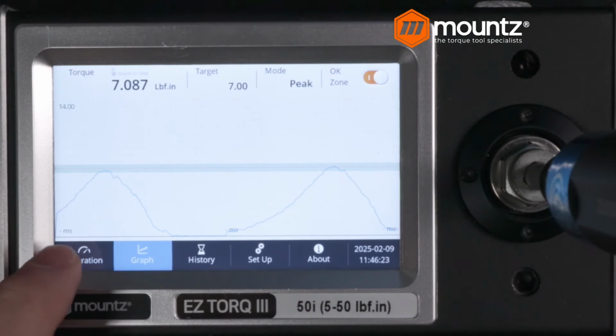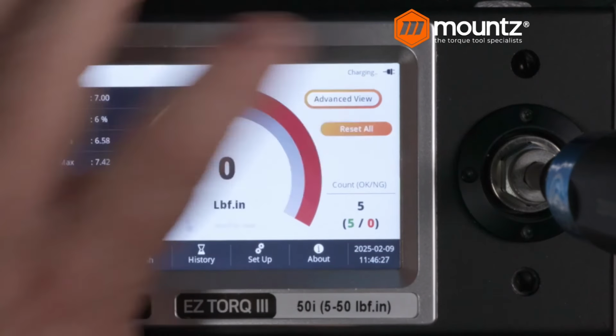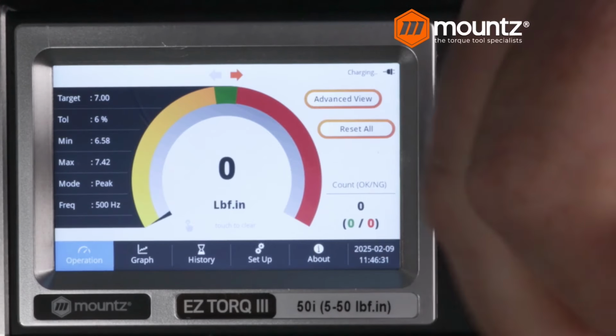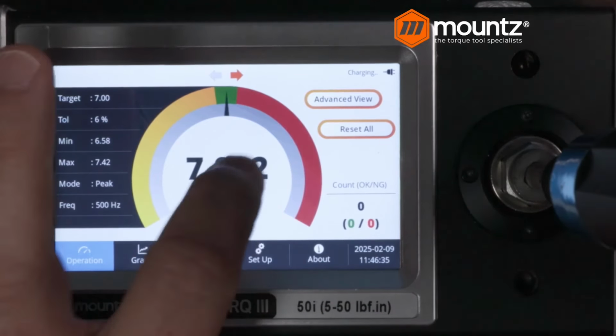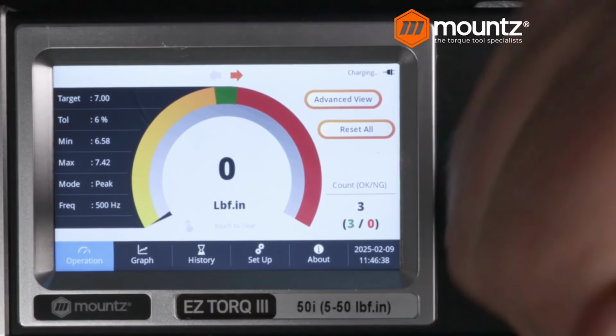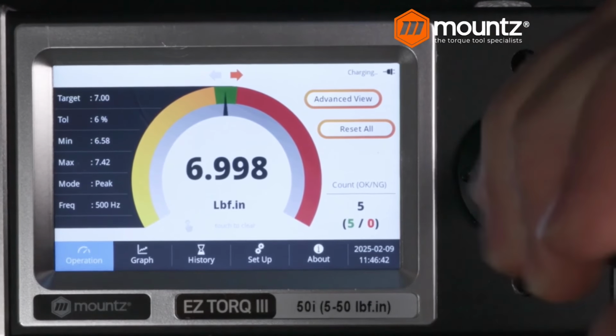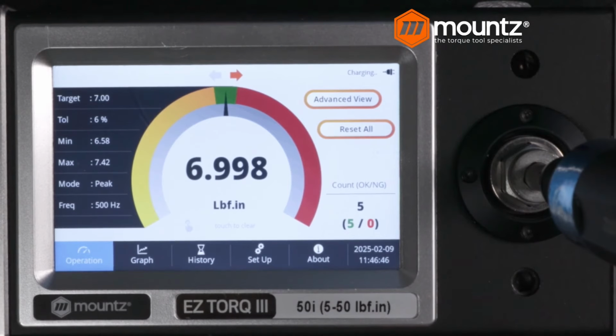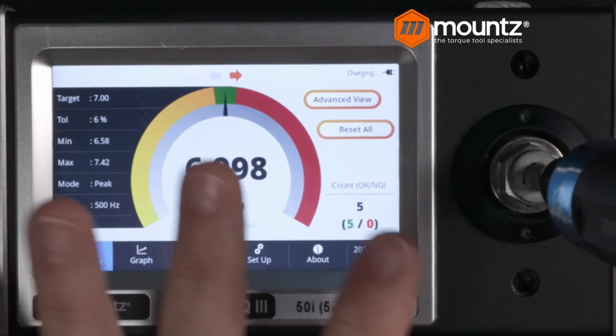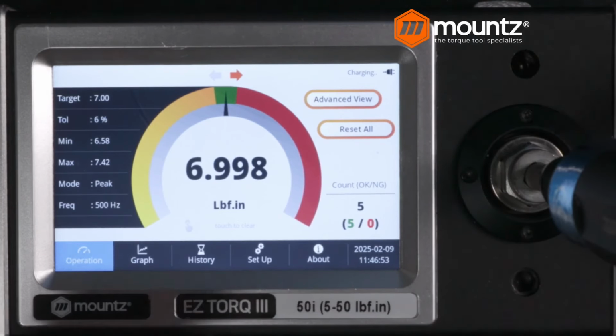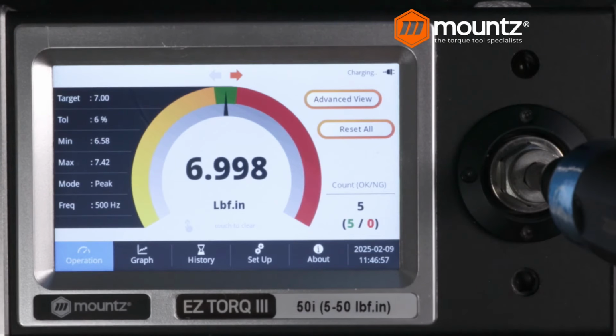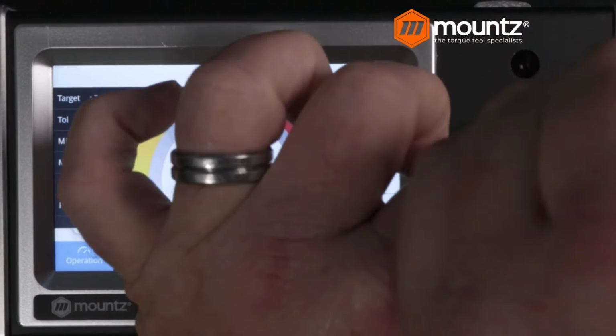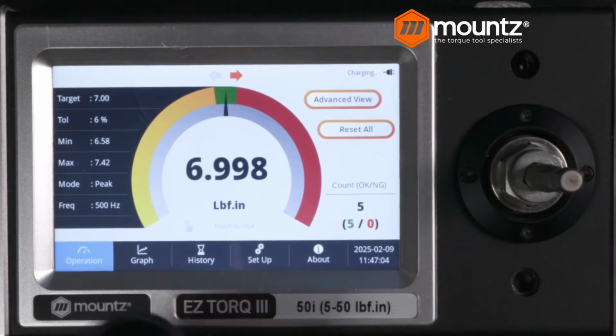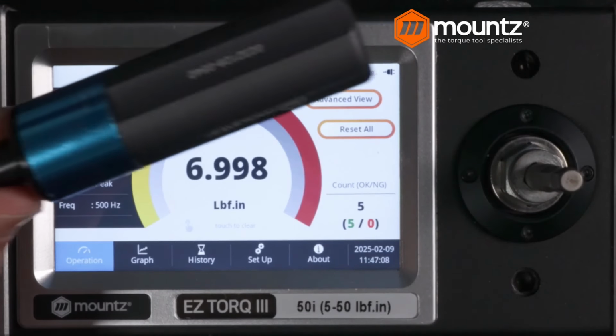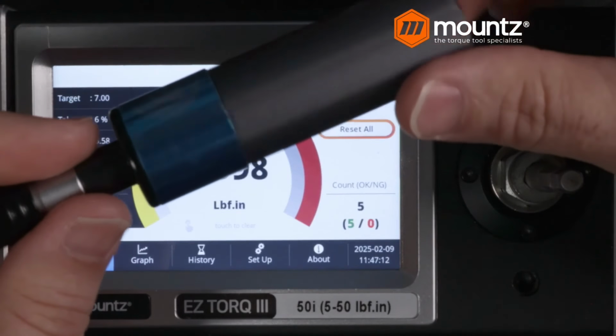Now if we come back to our operation screen, we can take our readings to see if this tool is still performing correctly. So 7 there. All right, perfect. Now we've taken our readings and everything looks great for this particular tool. Now, if we did need to make adjustments, if this tool was out of calibration and that was going to be part of our process, we can do that with this particular tool. This is a preset tool, obviously, because there's no scale on the outside of it, so it is set internally.